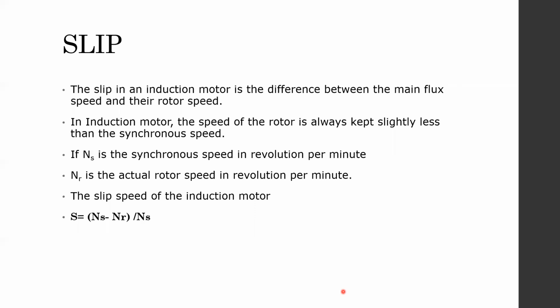What do you mean by slip? The slip in the induction motor is the difference between the main flux speed and the rotor speed. The speed of induction motor is always kept slightly less than the synchronous speed. If Ns is the synchronous speed and Nr is the actual rotor speed, then the slip is given as s = (Ns - Nr) / Ns.